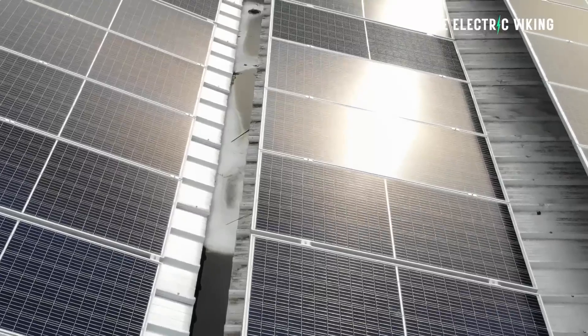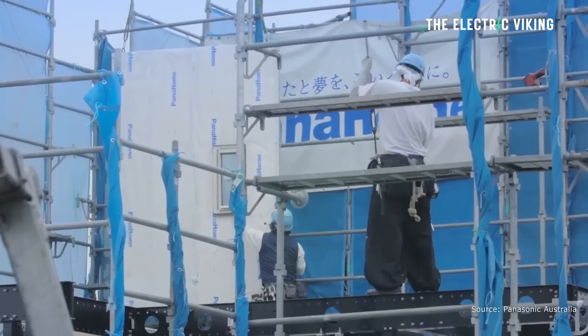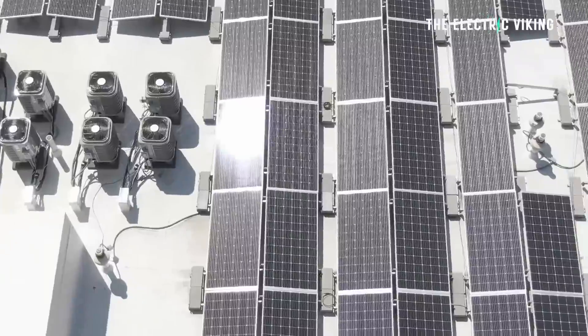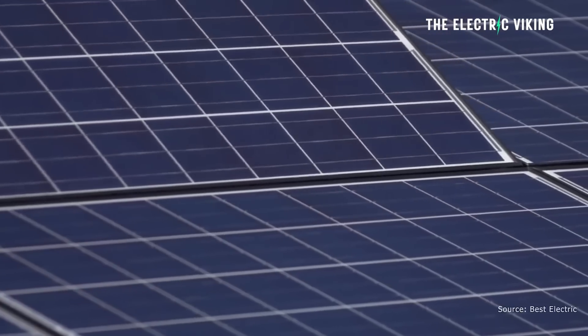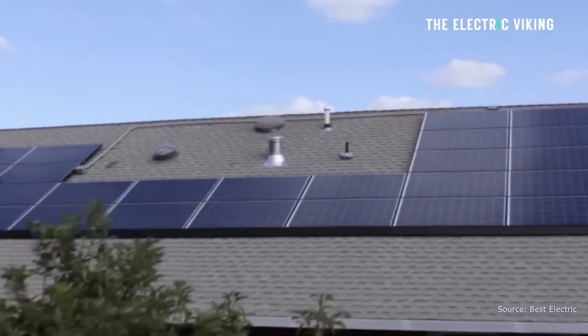The storage system includes a hybrid inverter, a lithium ferrophosphate battery, and the smart box — a home energy management device. Each battery is a modular pack in increments of 4.6 kilowatt hours of usable energy, offering up to 18.4 kilowatt hours per battery. If you buy the 18.4 kilowatt hour pack, you're actually getting four of the 4.6 kWh modules together. Up to four Evervolt batteries can be connected to one smart box, achieving up to 30 kilowatts of power and 72 kilowatt hours of usable energy.